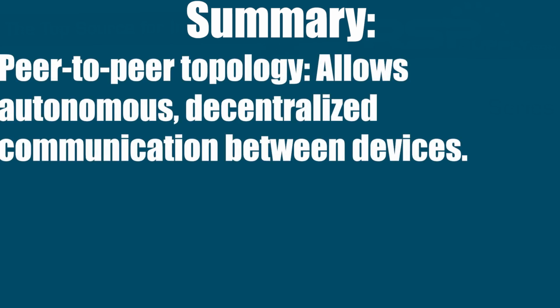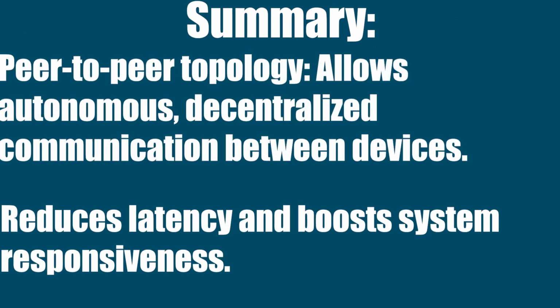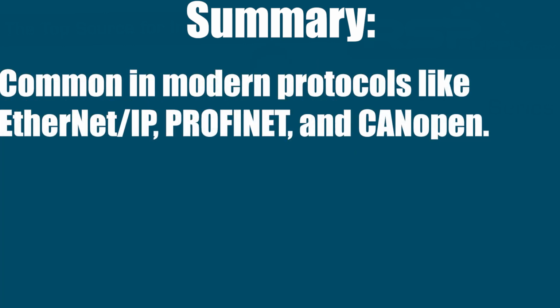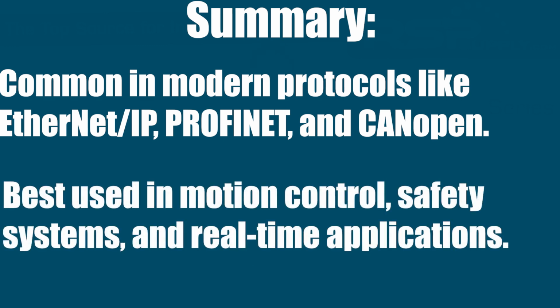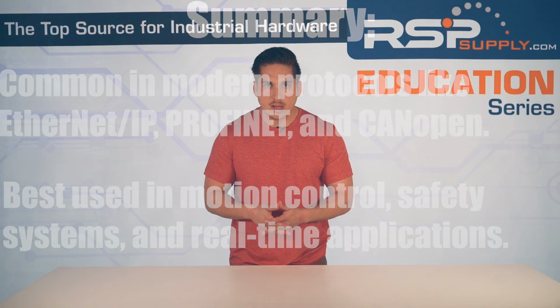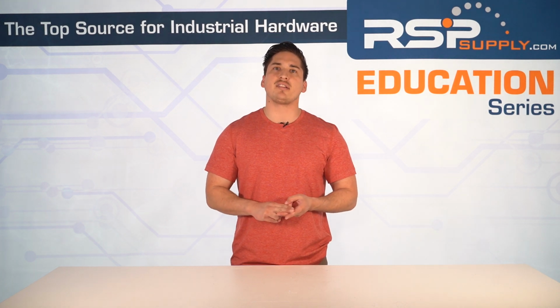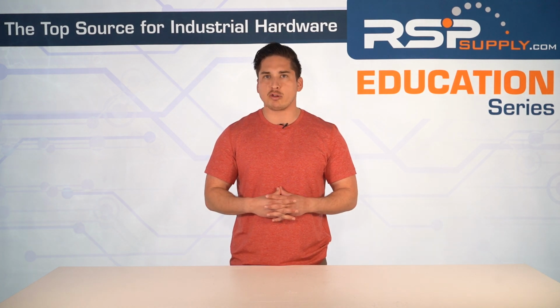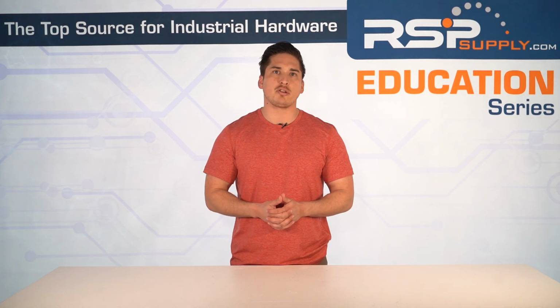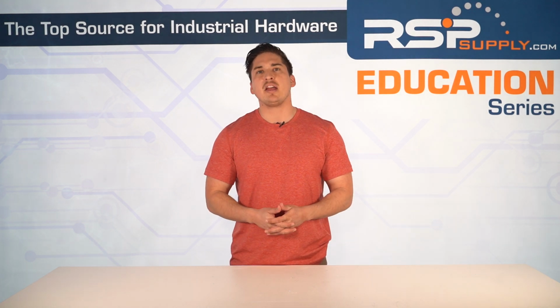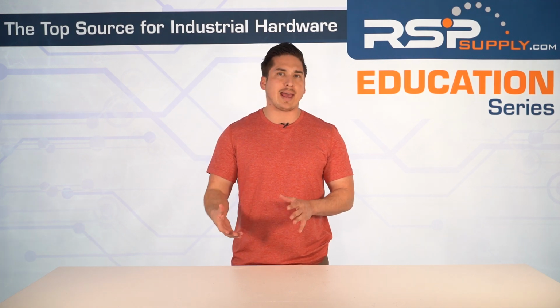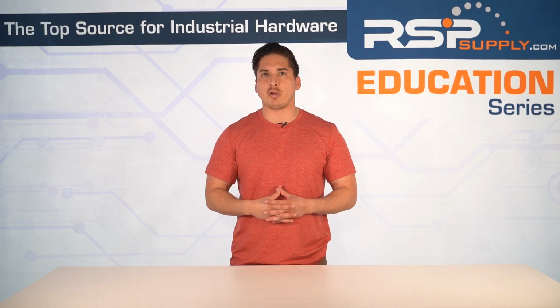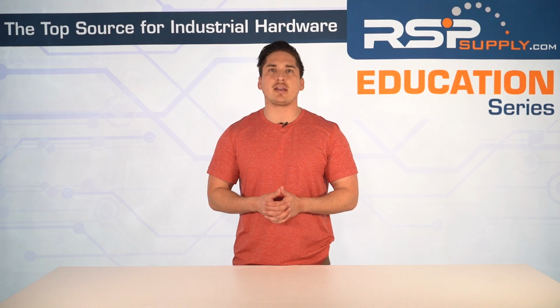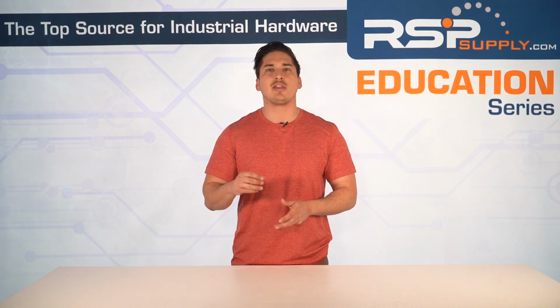So to summarize, peer-to-peer topology allows autonomous, decentralized communication between devices. It reduces latency and boosts system responsiveness. Very common in modern protocols like Ethernet IP, Profinet, CANopen. Best used in motion control, safety systems, and real-time applications. To recap, peer-to-peer topology is going to allow devices to communicate directly without relying on a central controller. Fast, reliable solution for real-time control, motion systems, distributed automation, using protocols like Ethernet IP, Profinet, and CANopen. Although it does require more advanced setup and careful traffic management, the benefits in speed, scalability, and system responsiveness make it a powerful option in the right applications.